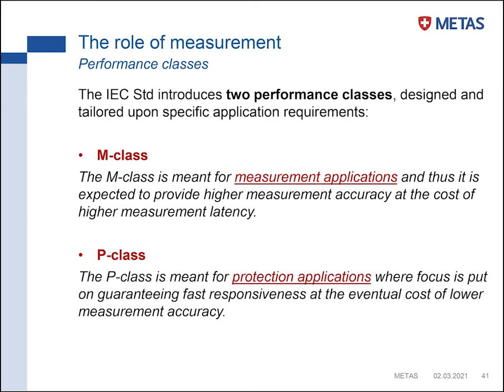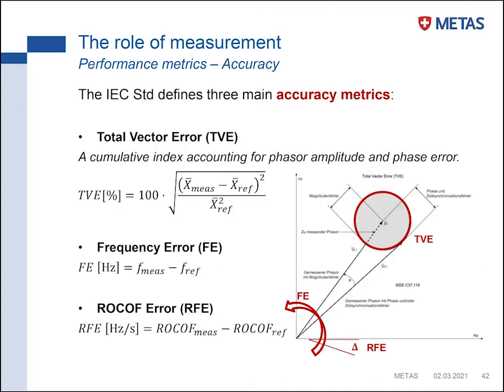And in particular, in the standard, we have two performance classes that are tailored upon specific application requirements. The M class, that is for measurement application, that is expected to be much more accurate and that accepts higher latency. So we don't need fast measurement, but we need high accuracy. Or the protection class, the P class, where the focus is put on fast responsiveness rather than high accuracy.